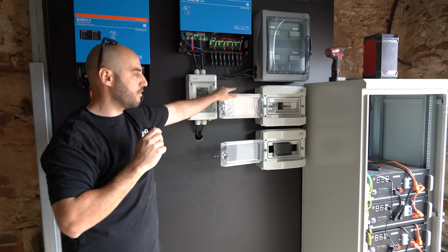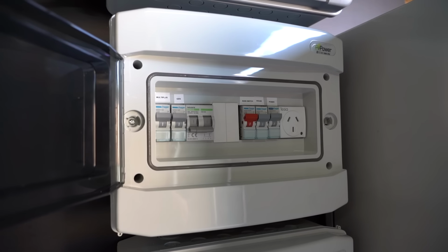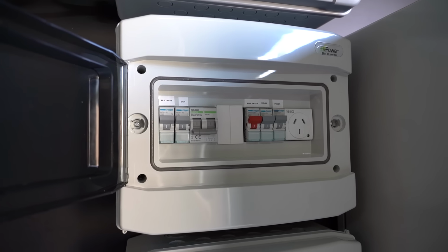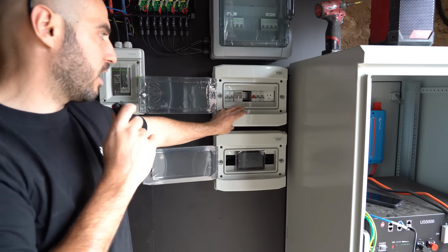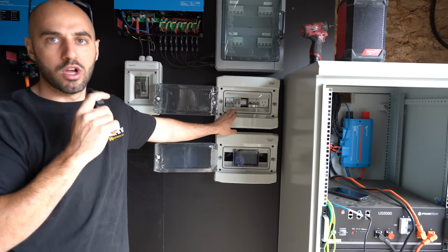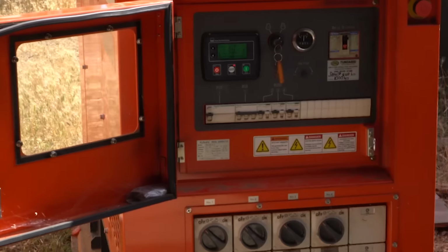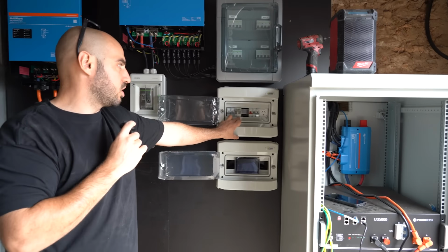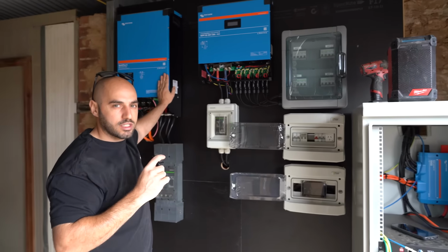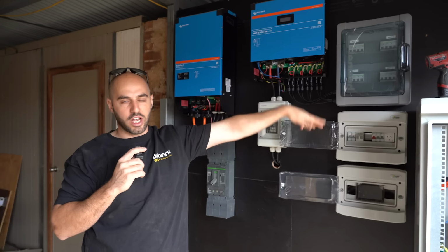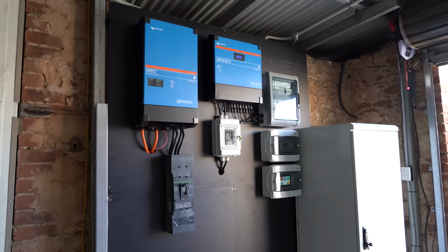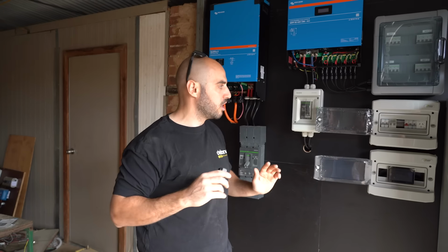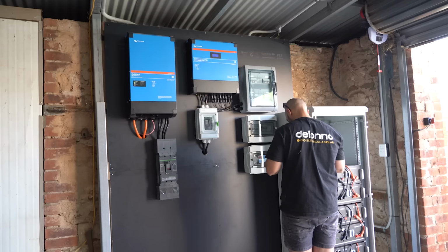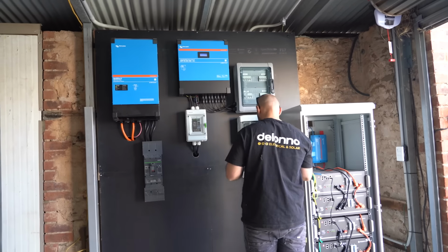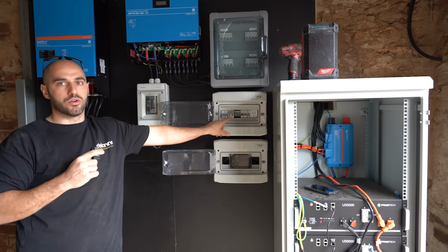Under that we have the AC switchboard. In here we have a few circuit breakers for the MultiPlus, including one for the generator input, plus a changeover switch. The changeover switch is really important — if the MultiPlus dies, we've built in redundancy where we can change over the supply so the house and property can run solely on the generator. It's really important to do this in off-grid setups because sometimes we can't get there straight away, so we build the redundancy in.